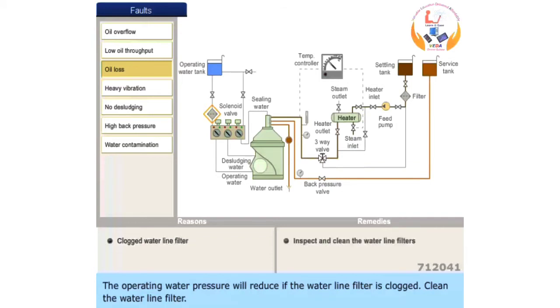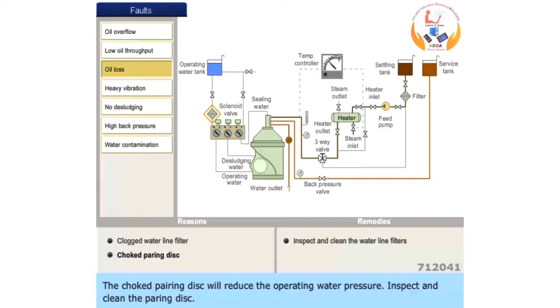Clean the water line filter. The choked paring disk will reduce the operating water pressure. Inspect and clean the paring disk.